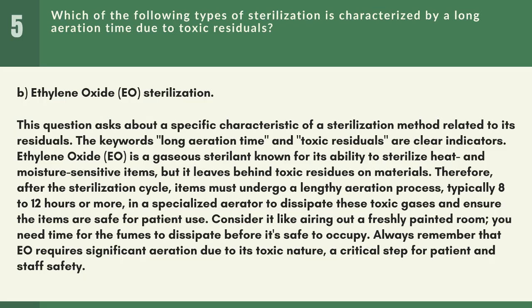behind toxic residues on materials. Therefore, after the sterilization cycle, items must undergo a lengthy aeration process, typically 8 to 12 hours or more, in a specialized aerator to dissipate these toxic gases and ensure the items are safe for patient use.